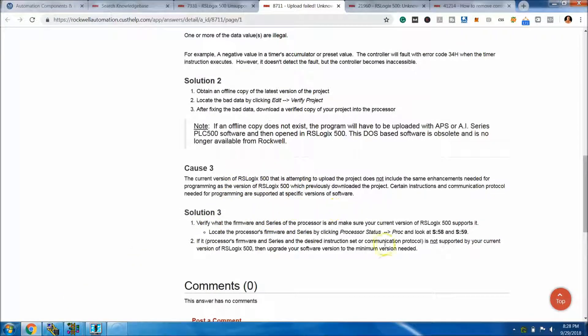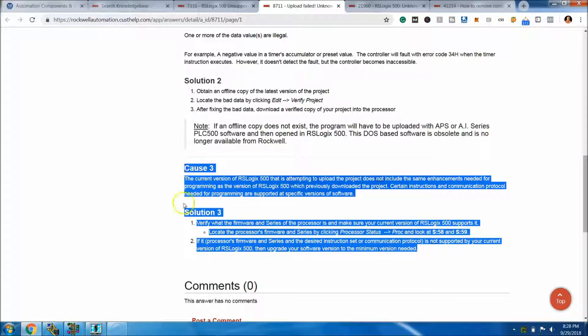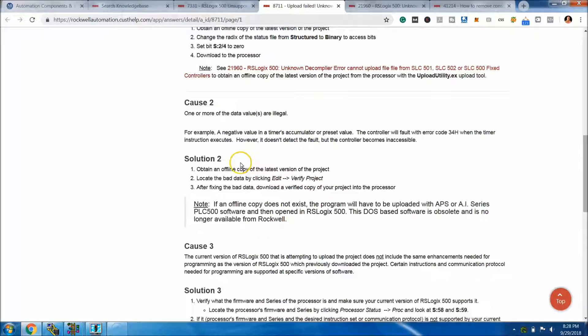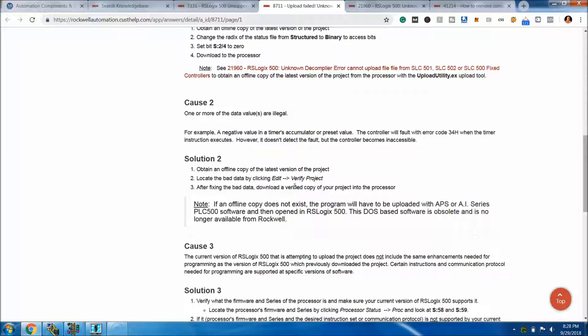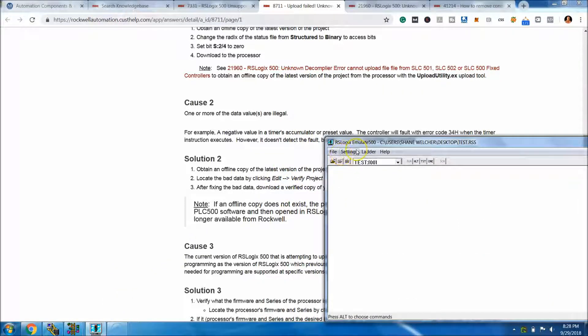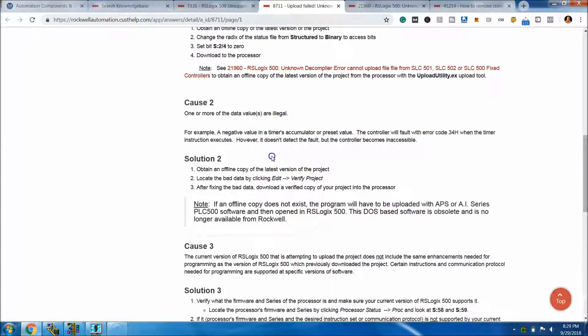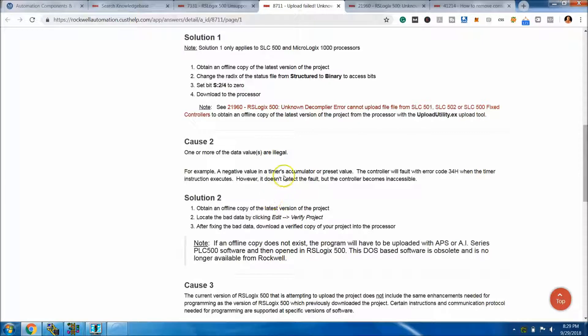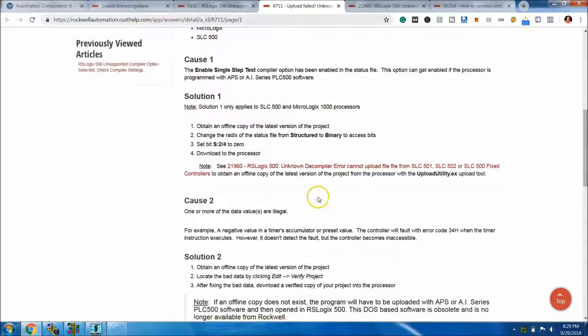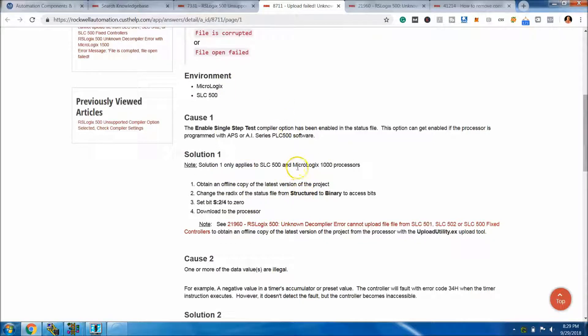This is just something to check. I would check the third cause right here. The second cause, obviously you would have a programming issue if you had that problem, so verify your data. You can basically do that by testing it, making a new file, saving it, and then downloading it again or going online with it. Meaning, make a new file, load it in the emulator, then point the emulator to the new file, and then go online with it. That would solve this issue. The first more common one is this S:2/4.